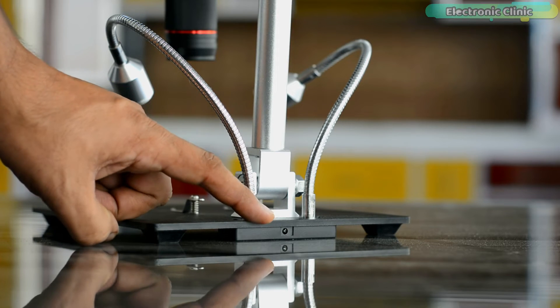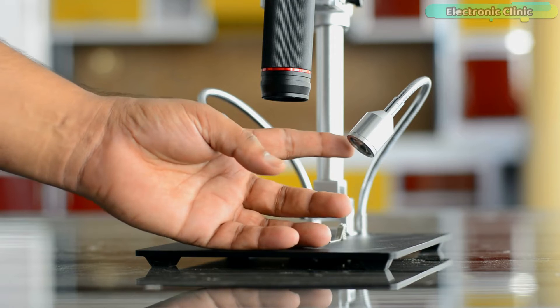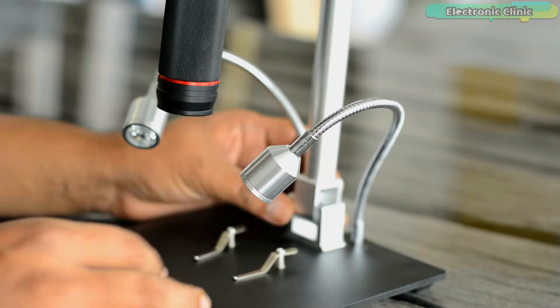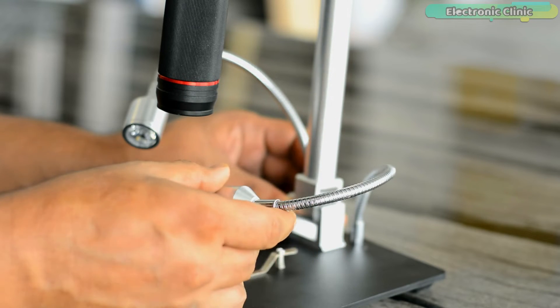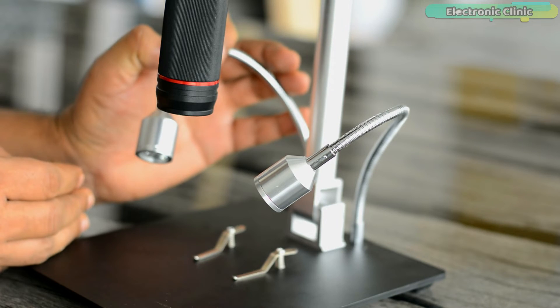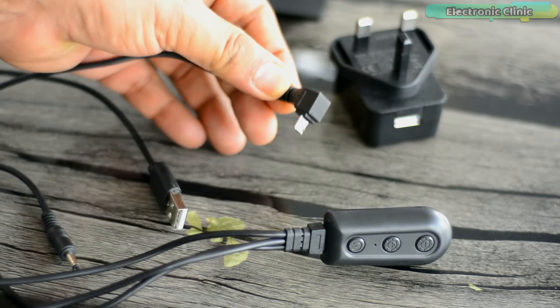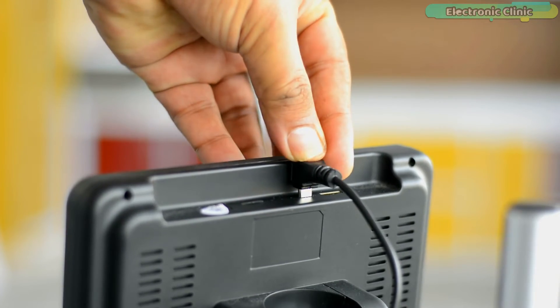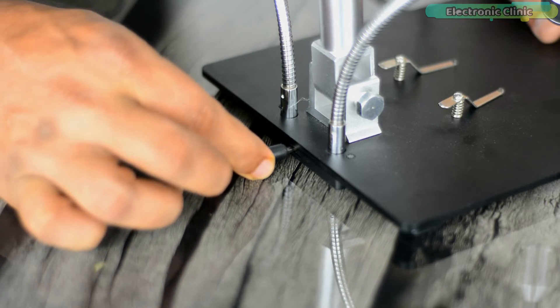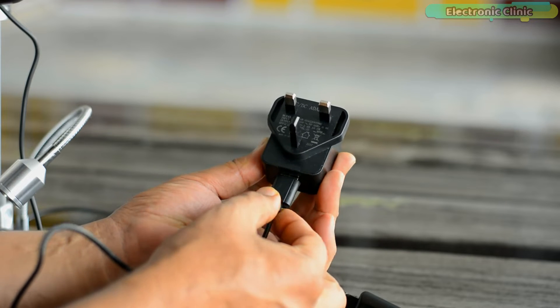On the bottom is the input power jack, which is used to power up the two metal base plate side lights. A total of 8 intensity levels of LED lights can be controlled using the plus and minus buttons on the power cable. The light body can be bent and the angle can be adjusted to meet different requirements for image brightness and lighting angle to get the best image effect. Plug the USB into the microscope monitor USB interface, use the spotlight interface to power up the LEDs, then plug the USB into the AC to DC adapter to supply the required voltage.